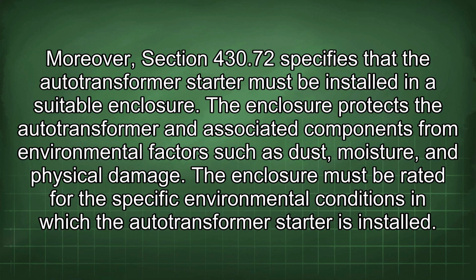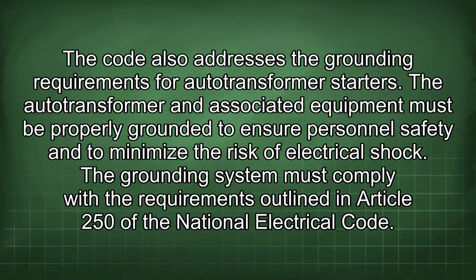Moreover, Section 430.72 specifies that the autotransformer starter must be installed in a suitable enclosure. The enclosure protects the autotransformer and associated components from environmental factors such as dust, moisture, and physical damage. The enclosure must be rated for the specific environmental conditions in which the autotransformer starter is installed. The code also addresses the grounding requirements for autotransformer starters. The autotransformer and associated equipment must be properly grounded to ensure personnel safety and to minimize the risk of electrical shock. The grounding system must comply with the requirements outlined in Article 250 of the National Electrical Code.